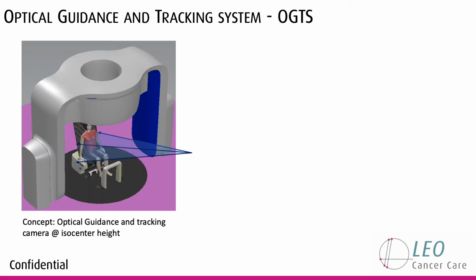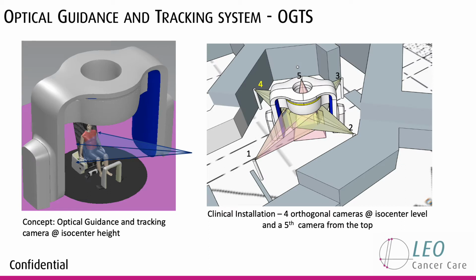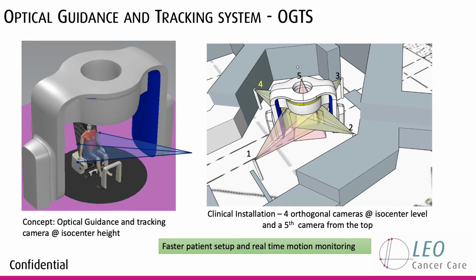So this slide shows the installation of our optical tracking system that we're developing ourselves with a company in Knoxville. You can see on the left picture here is just a graphic illustration of the mounting position of one camera at the isocenter level, and we can see how we get a beautiful unobstructed view of the patient in that direction. Then we can mount 4 cameras in a similar position as indicated there, with positions 1, 2, 3, and 4, and even a 5th camera from the top. Important to note that these cameras are exactly 90 degrees apart. So we end up with a complete orthogonal system, and the beautiful thing is that if the patient would, for example, be facing directly into one of the cameras by rotating the positioner through 45 degrees, the other camera will see the patient exactly from the side. So if you show those images to the patient or to the therapist, it should be very easy to align the patient left, right, or forward, backward at any specific moment.